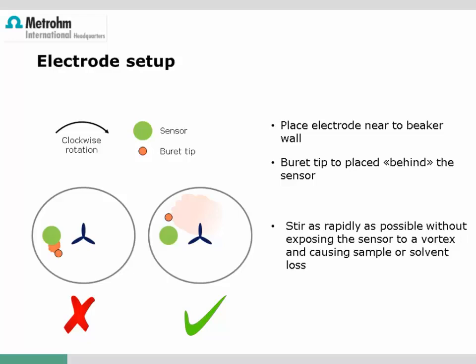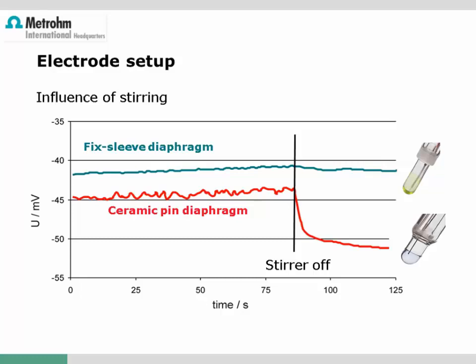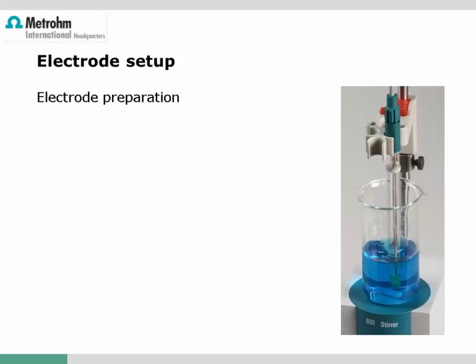Stirring should be as fast as possible, but a vortex should be avoided since the sensor might not remain fully immersed or the sample solution may spill. Beaker and stirrer sizes should be fixed and not changed, otherwise stirring efficiency may vary. The effect of stirring can be shown with a practical example using deionized water: once the stirrer is switched off, a fixed-sleeve electrode provides a stable signal, whereas a significant signal drop is observed for an electrode with a ceramic pin diaphragm. Therefore, we strongly recommend always working at the same stirring speed and using fixed-sleeve electrodes for pH titrations to a fixed endpoint.